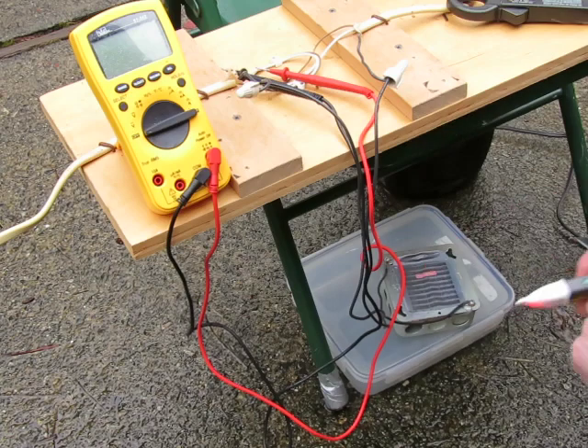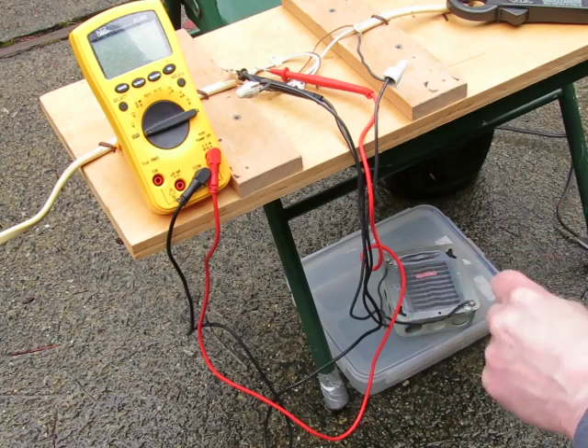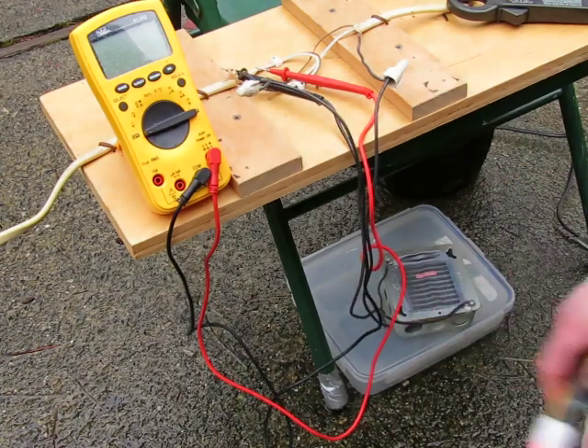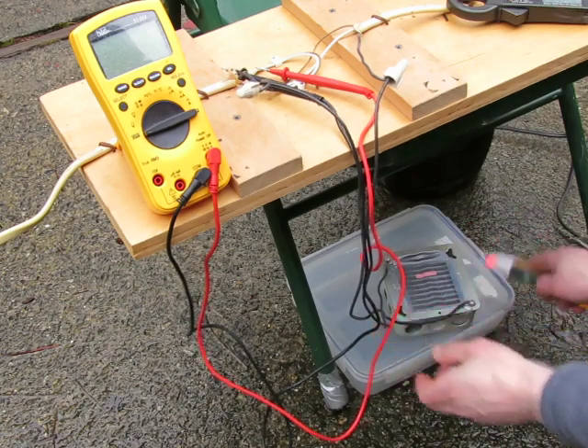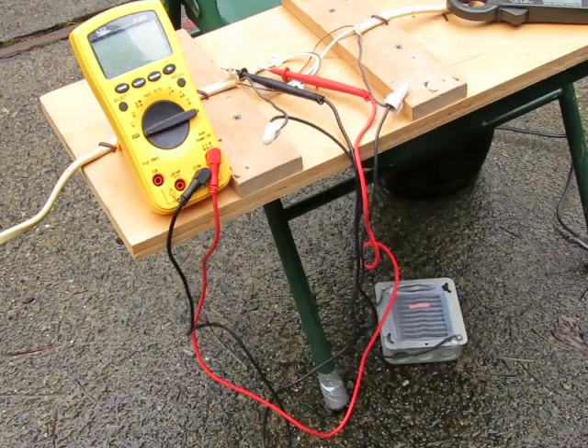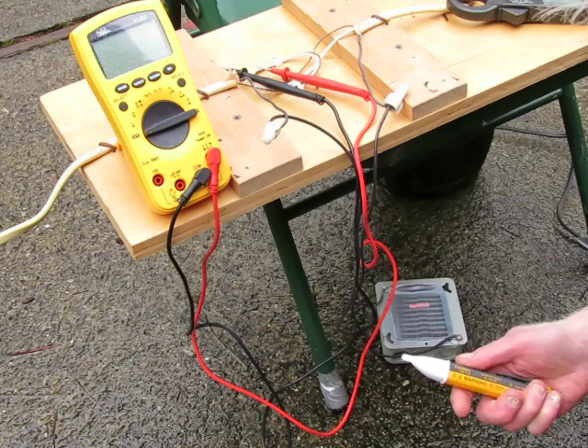What about when it's grounded — sitting right on the ground, buried in dirt, or for some other reason the case is grounded — will this work? This usually won't; it will only work on ungrounded conductors, so we'll see. We'll take it off its isolation here and set it right on the ground, and you'll see that it clearly still does light up the NCVT.